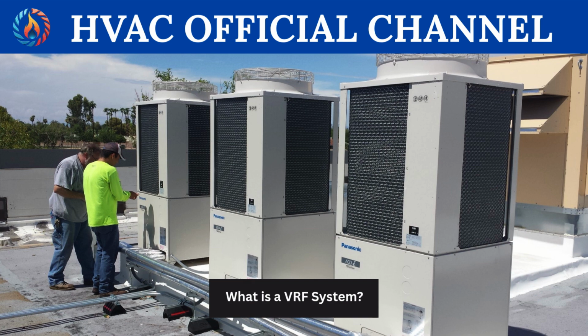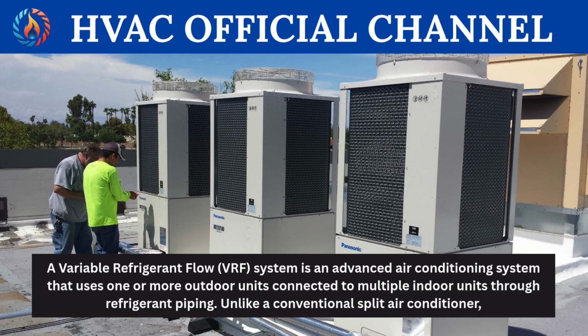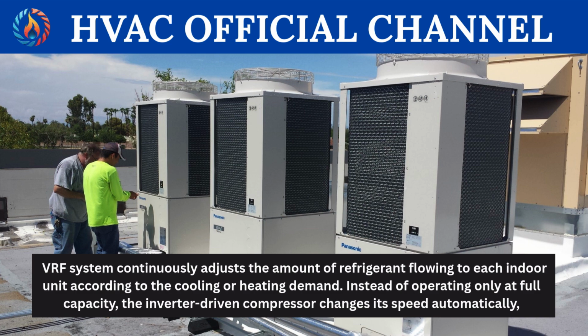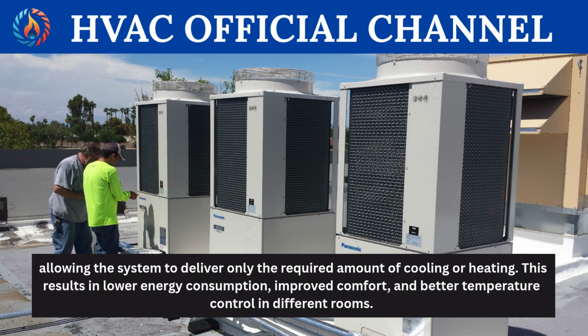Let's begin. What is a VRF system? A variable refrigerant flow (VRF) system is an advanced air conditioning system that uses one or more outdoor units connected to multiple indoor units through refrigerant piping. Unlike a conventional split air conditioner, a VRF system continuously adjusts the amount of refrigerant flowing to each indoor unit according to the cooling or heating demand. Instead of operating only at full capacity, the inverter-driven compressor changes its speed automatically, allowing the system to deliver only the required amount of cooling or heating. This results in lower energy consumption, improved comfort, and better temperature control in different rooms.